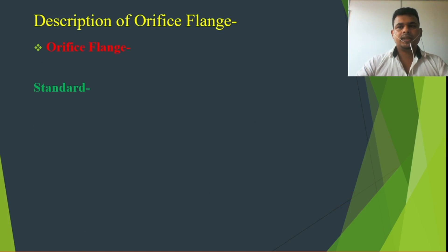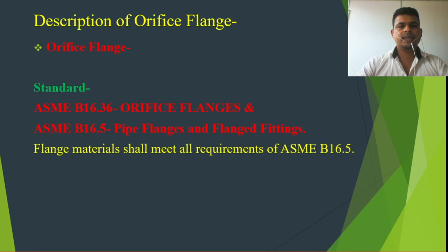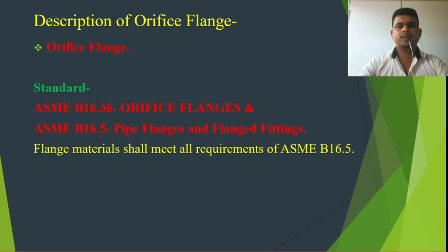Regarding standards: ASME B16.36 is used purely for the orifice flange, and we also need to use ASME B16.5 for pipe flanges and flange fittings. Flange material shall meet all requirements of ASME B16.5. Flange rating and flange thickness follow ASME B16.5, while for the tap holes, jack screws, and orifice plate provisions, we follow ASME B16.36.